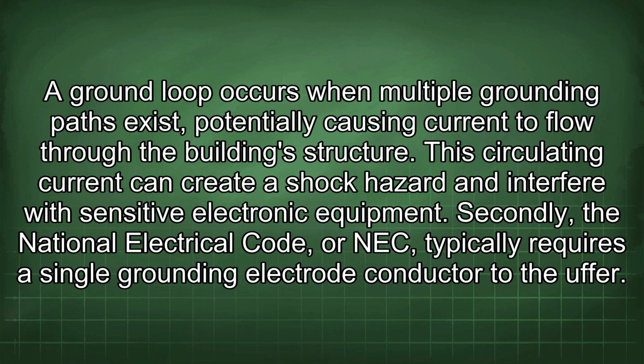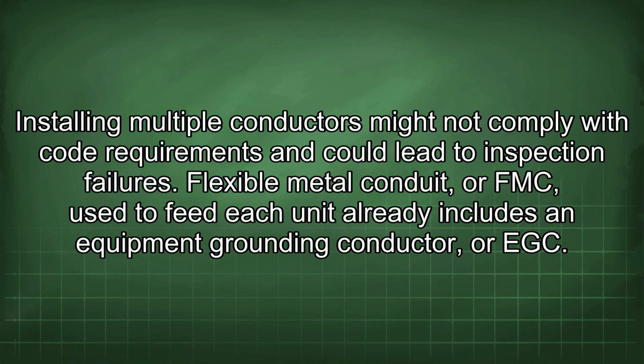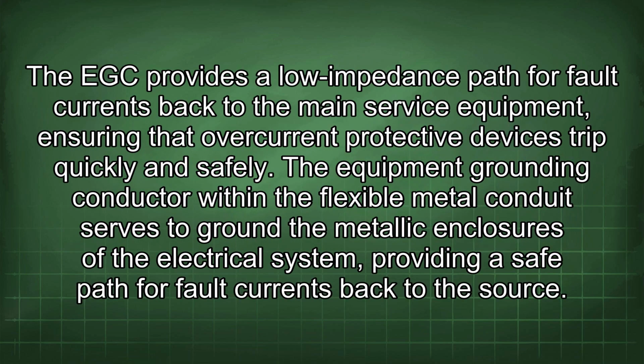Secondly, the National Electrical Code, or NEC, typically requires a single grounding electrode conductor to the Ufer. Installing multiple conductors might not comply with code requirements and could lead to inspection failures. Flexible metal conduit, or FMC, used to feed each unit already includes an equipment grounding conductor, or EGC. The EGC provides a low impedance path for fault currents back to the main service equipment, ensuring that overcurrent protective devices trip quickly and safely.